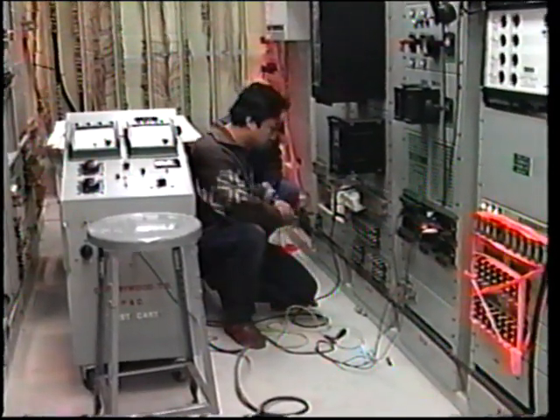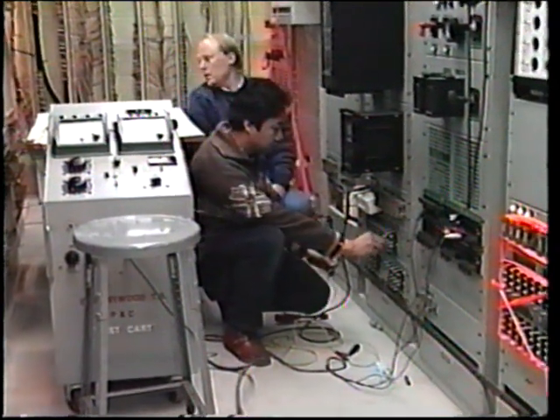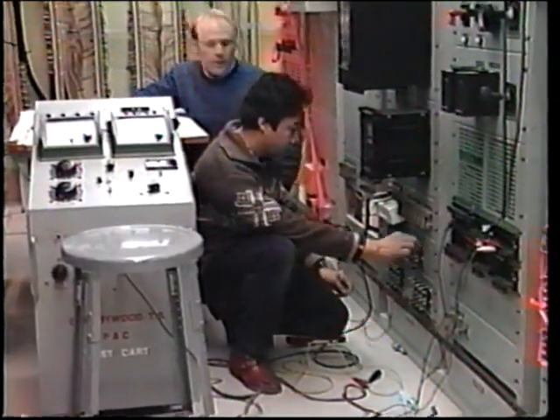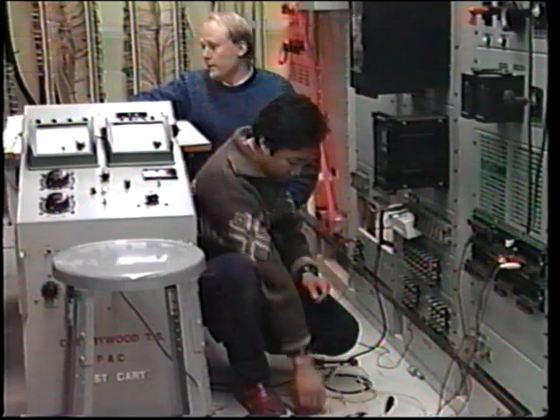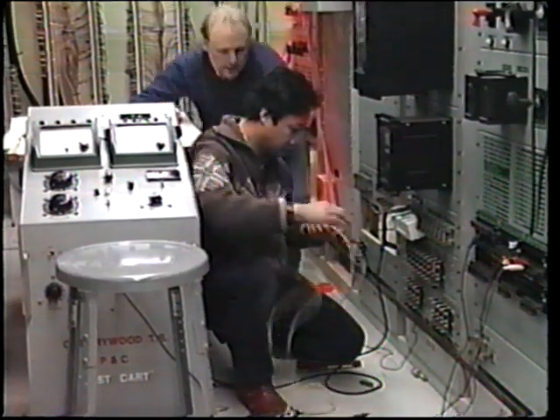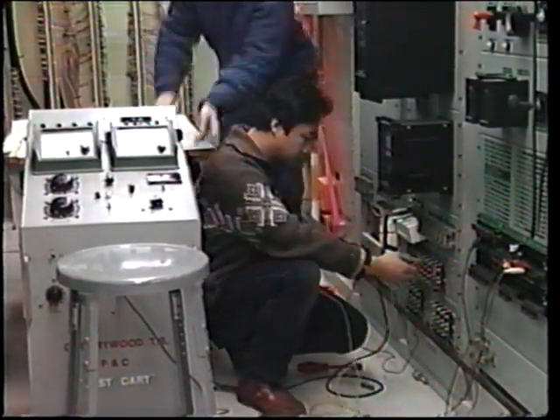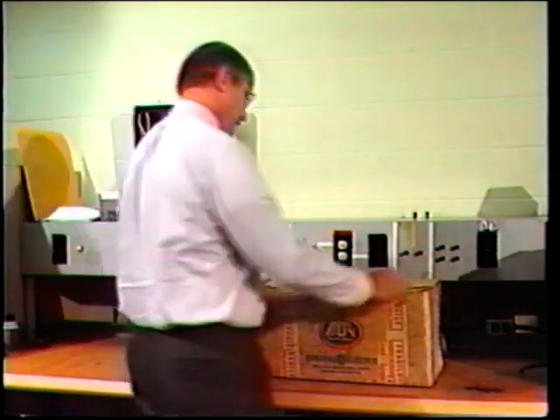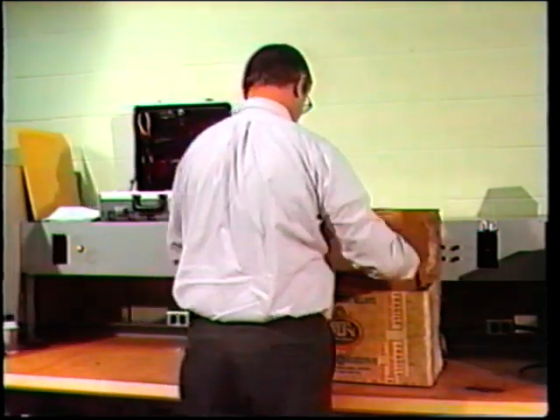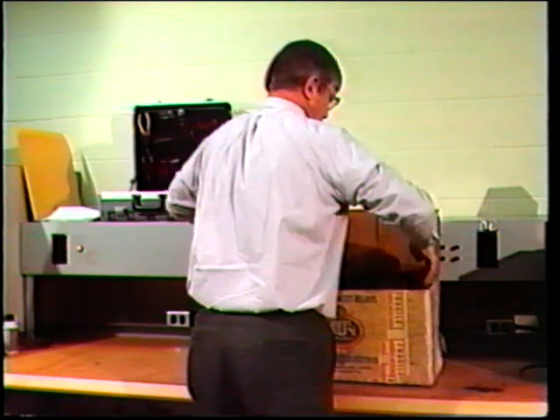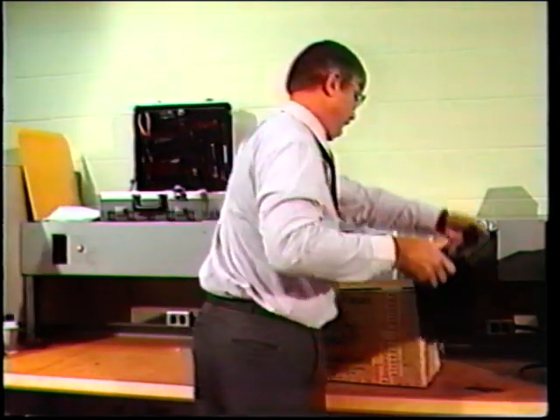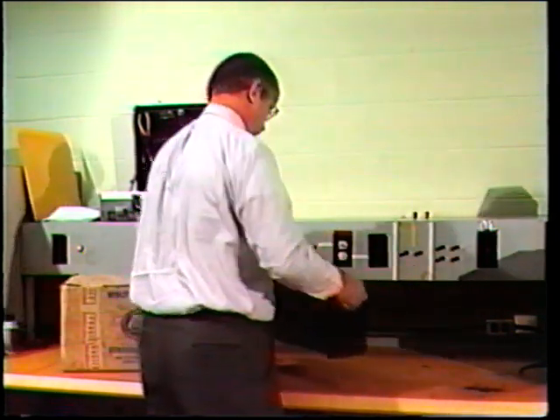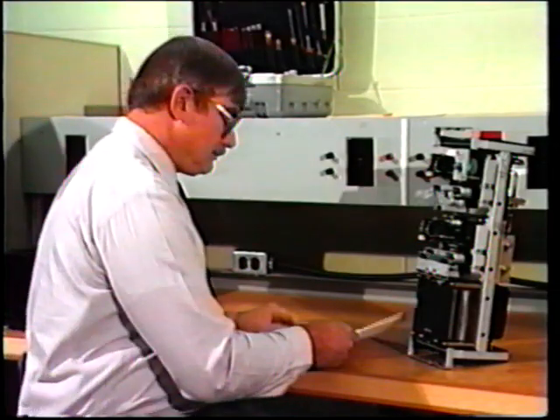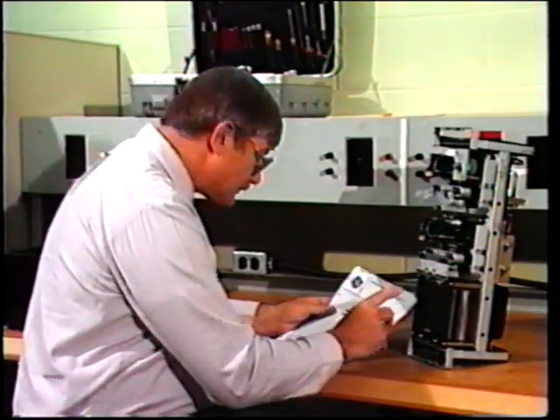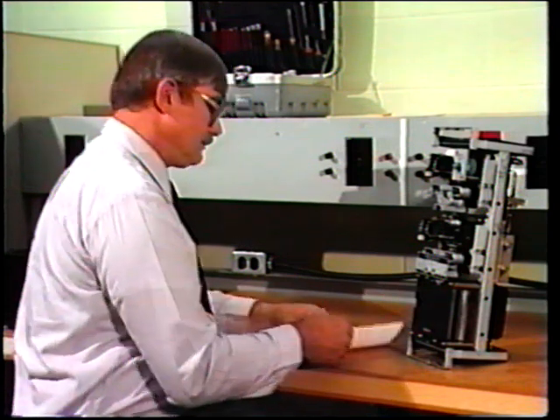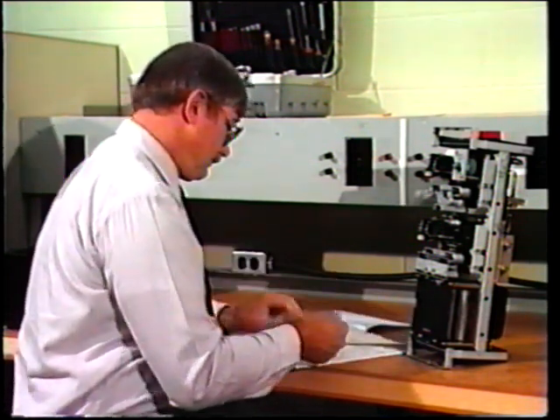The first item mentioned in the procedures is usually that of safety. This is a reminder to the technician to be aware of potential dangers associated with commissioning tests. The next item is a physical inspection of the protection equipment to make sure that equipment supplied by a manufacturer does in fact conform to the bill of material.